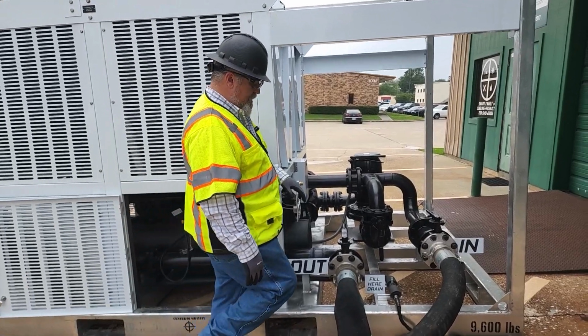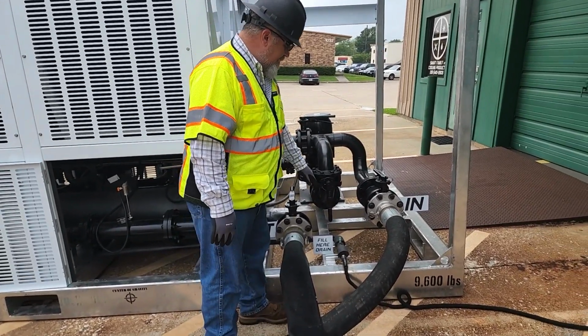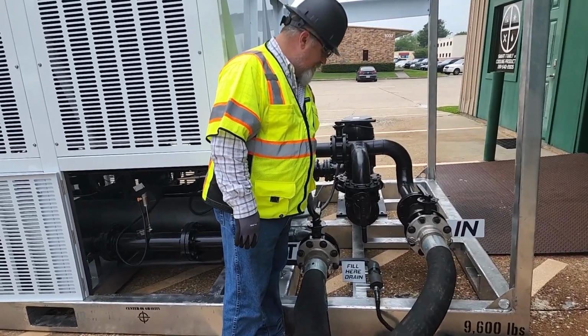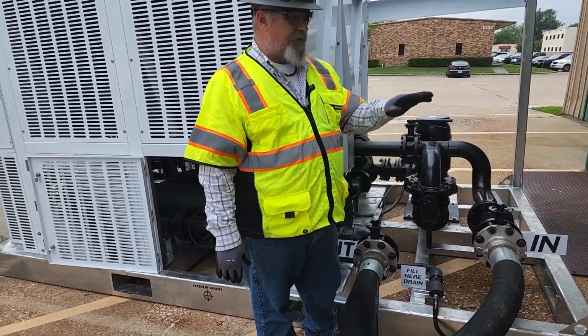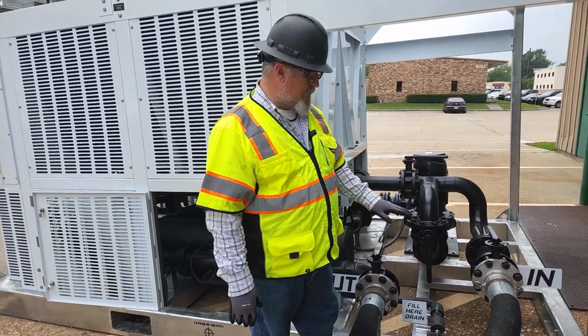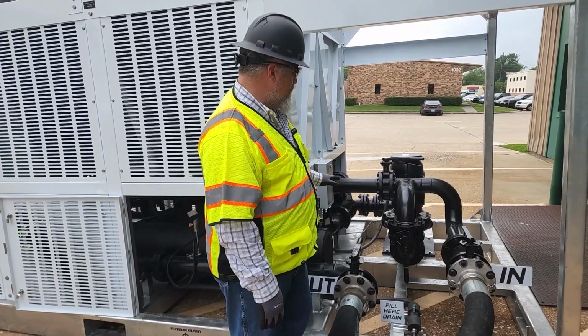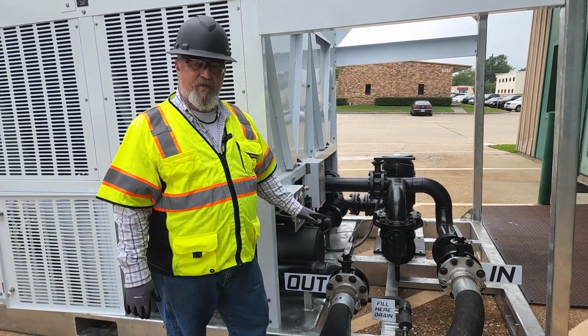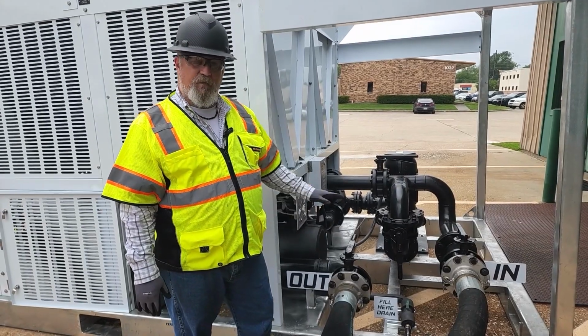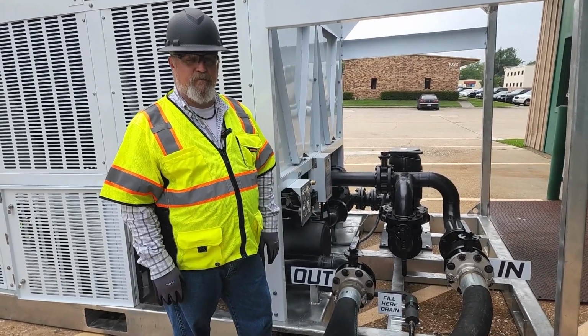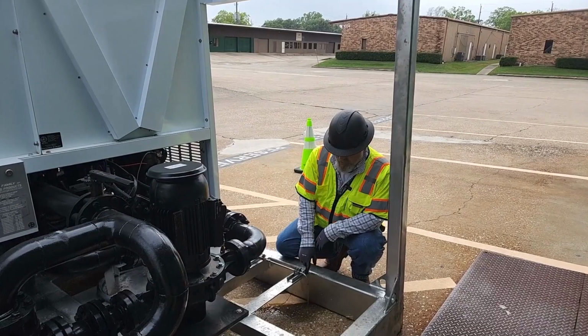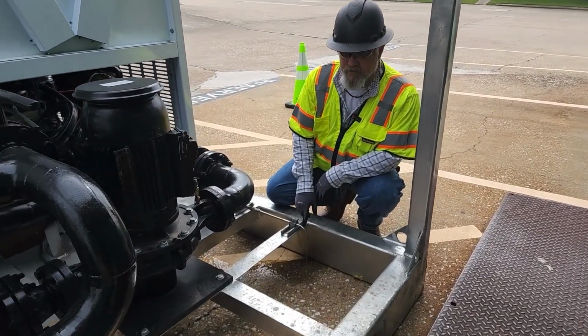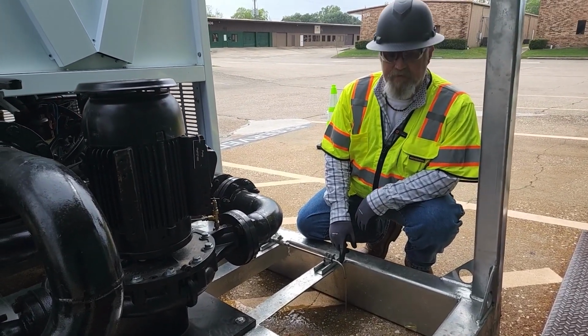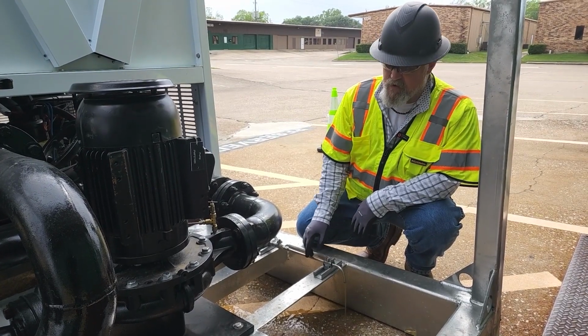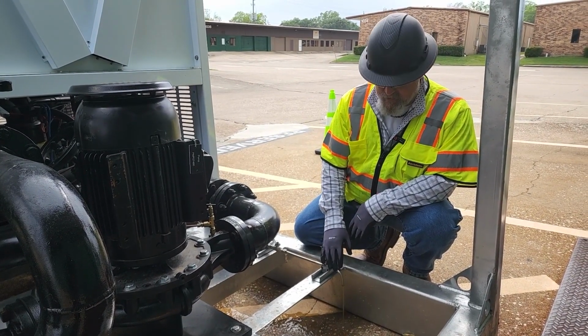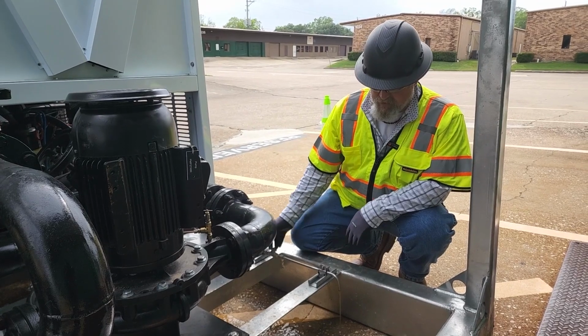Okay, so you can see that I've already attached our filler hose. I've got the ball valves in the open position, and I've already opened the butterfly valves. So I've turned the liquid on, and we are in the fill process now. So now we'll start watching our vents and our ball valves where we'll start bleeding water. All right, now you can see that our lowest water valve here has started flowing. Now I'm going to let that run for a few seconds to get out any trash, and if there's any air bubbles that are coming through there, I want that to get out. So I'm going to let that run for a few seconds, and then I'm going to close that off.